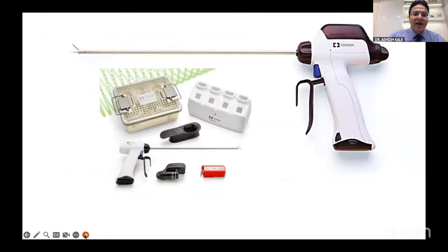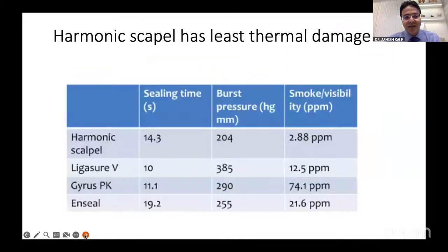Coming to the next, usually you have the battery chargers. You can use these easily, and they can go for more than 30 to 60 minutes. Once we come down to the importance of all these thermal energy sources, it is lateral energy spread and the burst pressure. What is the burst pressure? The burst pressure is when you are giving coagulation to a particular tissue. When you release the jaw, there is a spurting of the vessels. This has to get total coagulation formation.